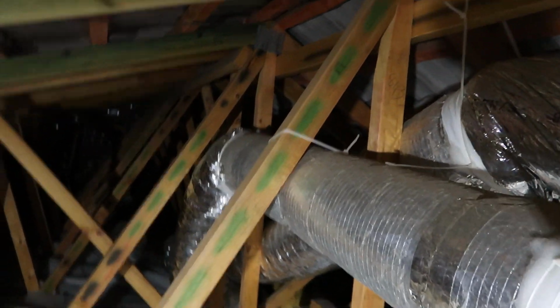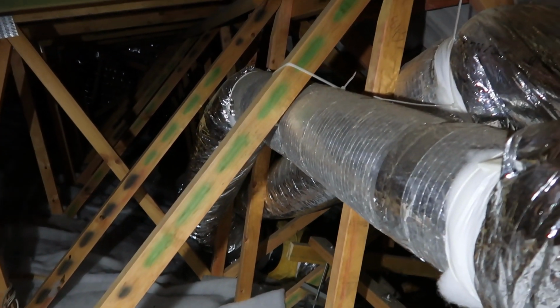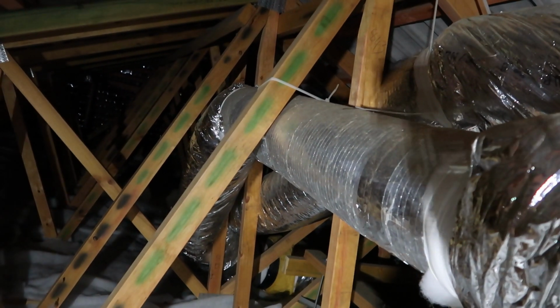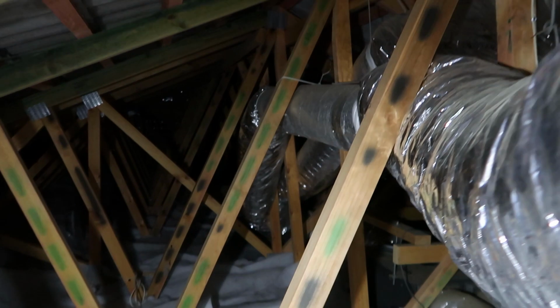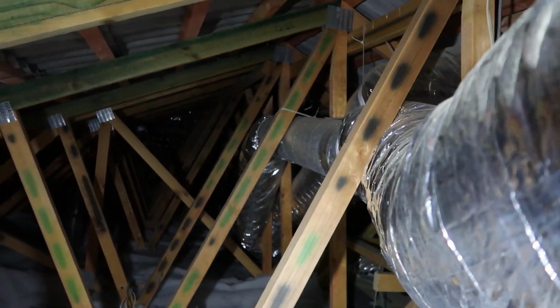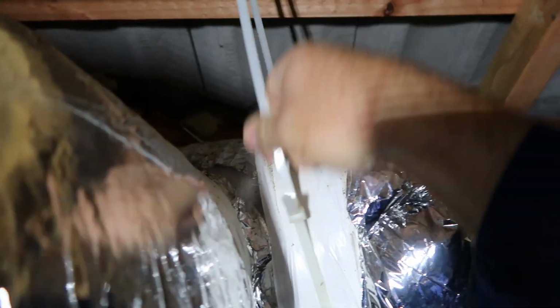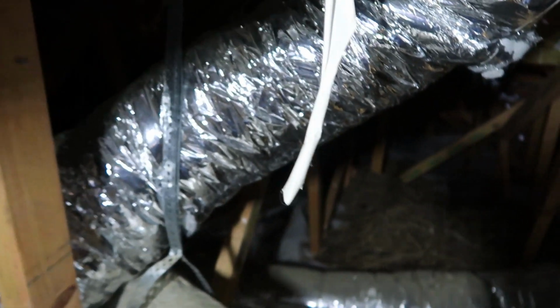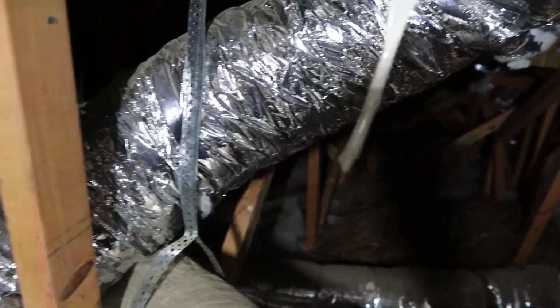And you notice I actually use insulated ducting. You see a lot of these cheap sets, they'll just have nude ducting, not insulated at all, and that really irks me, because the longer you run, the more heat energy you lose. See, like on this ducting here, I've used solid strap, I've used expensive strong sturdy cable ties to prop it up. I've seen a lot of electricians just use cable and just do knots and tie it off, or string, and then the string rots out and breaks, and that just irks me.